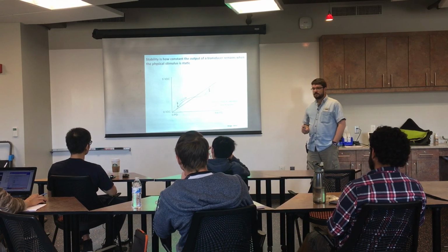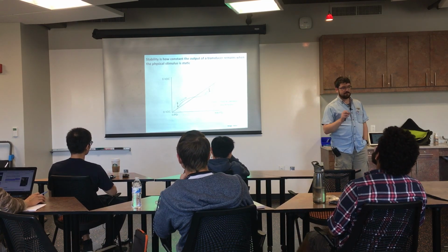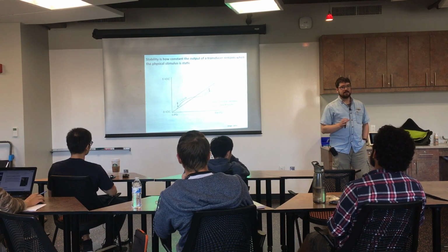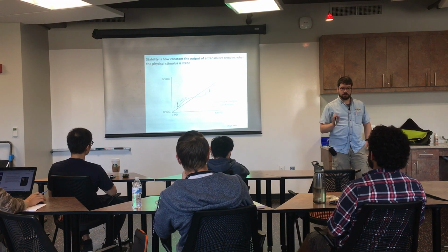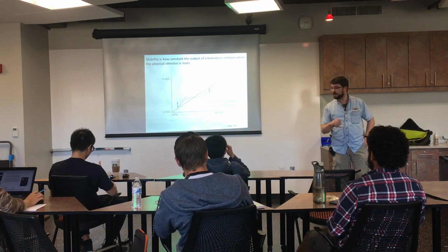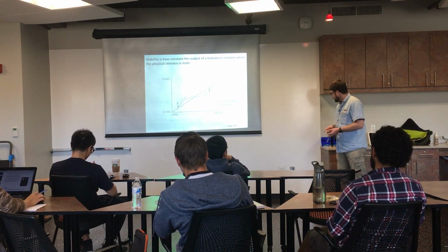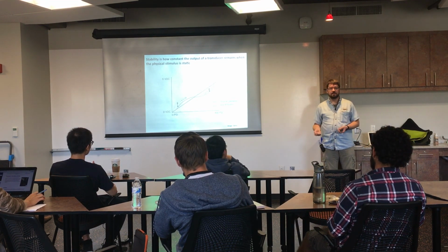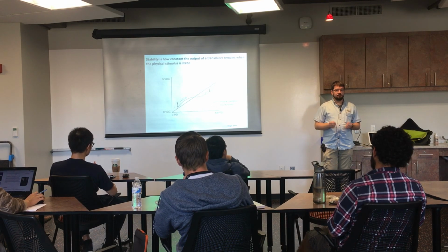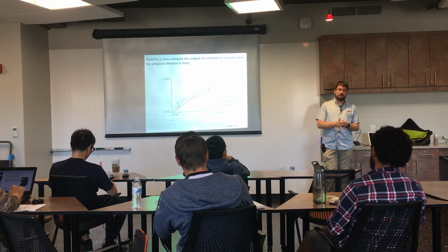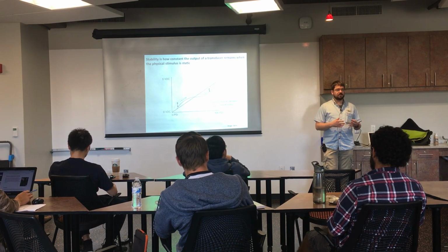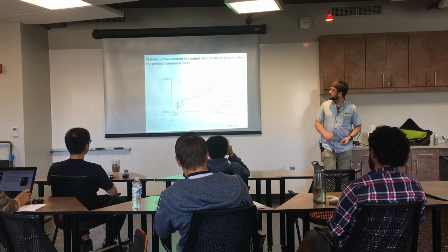The stability of a transducer is another one that's big, and for shorter lab experiments, this maybe isn't as much of a concern for one experiment, but between many experiments possibly. If you're having a field deployment, so you put a pressure sensor out somewhere in the ocean, you want to know that that transducer is going to be stable over months to years, that you're not going to have lots of long-term drift in what its calibration is or what its zero is.